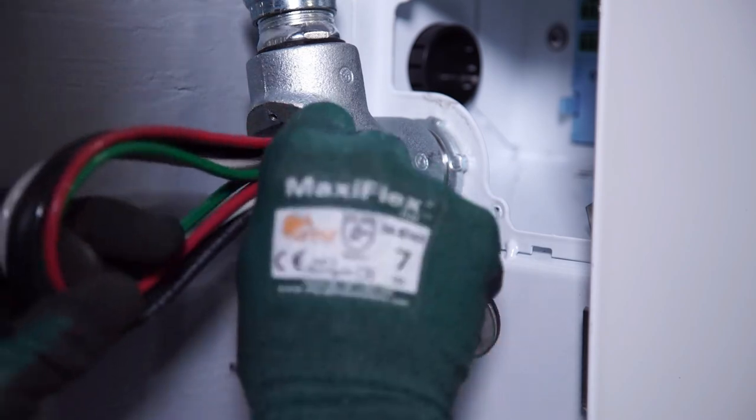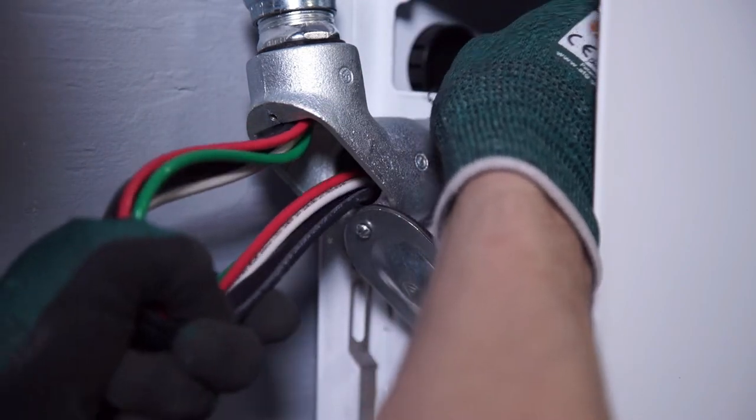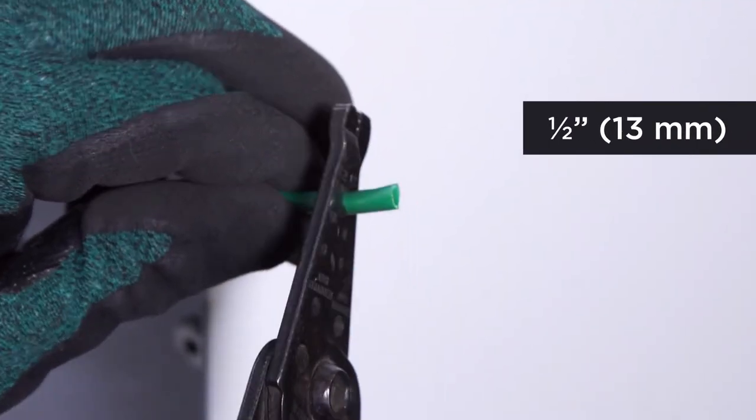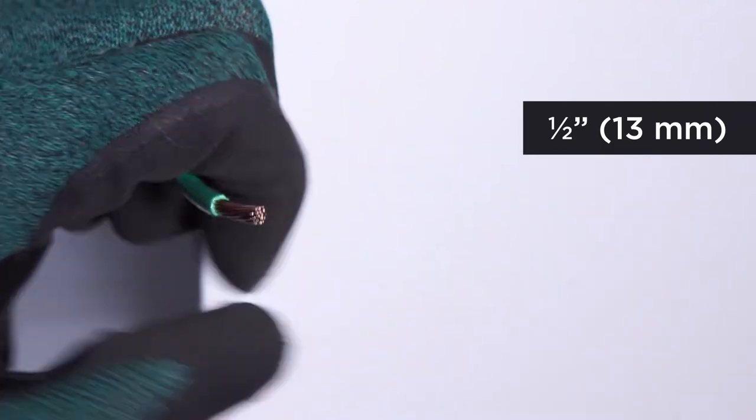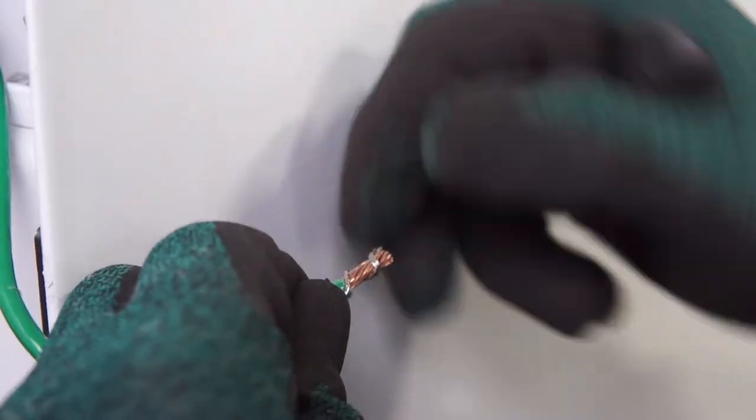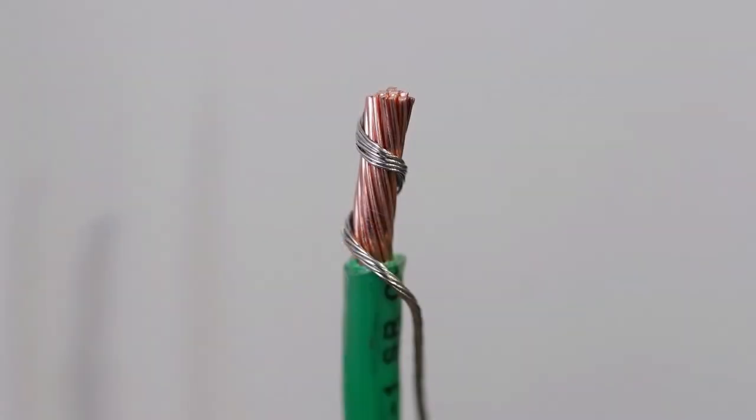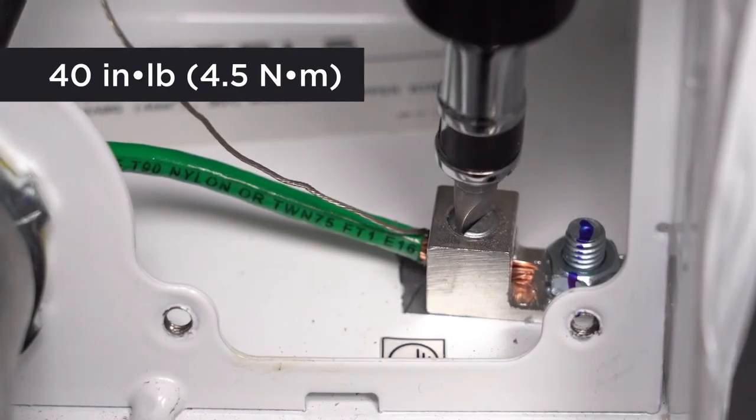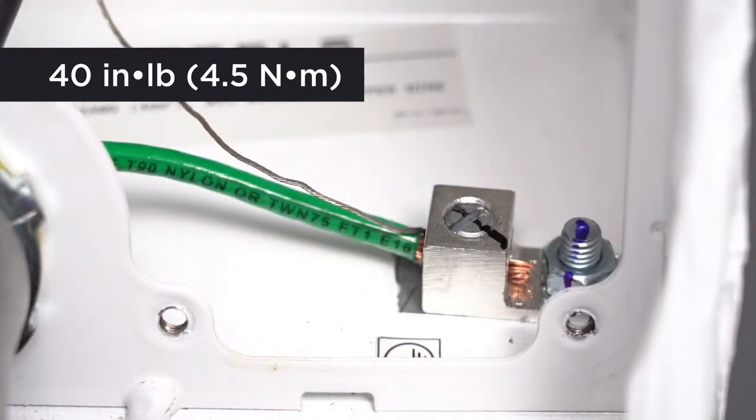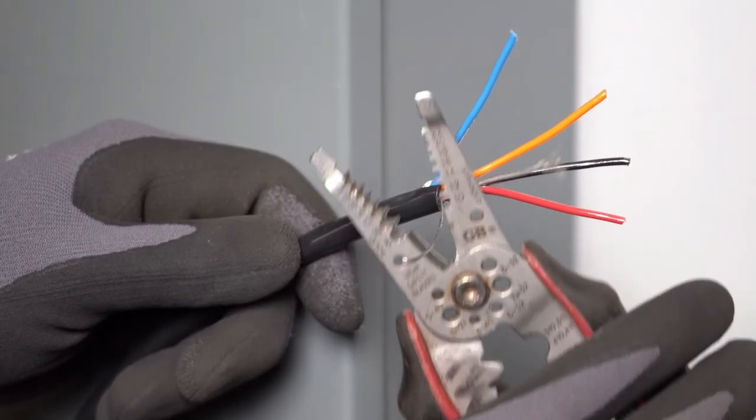Pull the equipment grounding conductor, AC conductors, and communication cables into the wiring compartment. Strip half an inch of insulation off the end of the equipment grounding conductor. Take the drain wire from the communication cable and twist it around the grounding conductor. Next, connect them both to the ground lug.